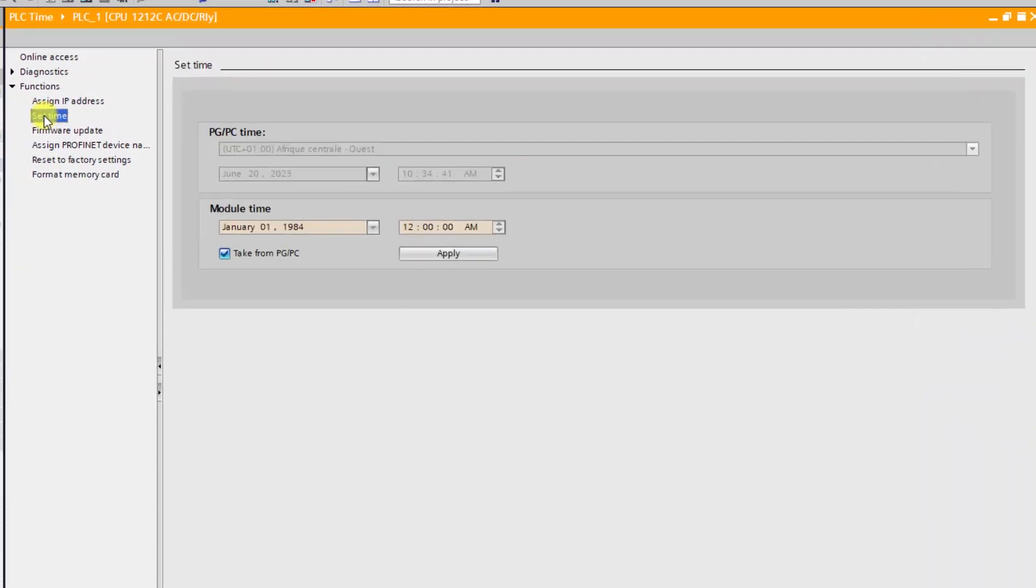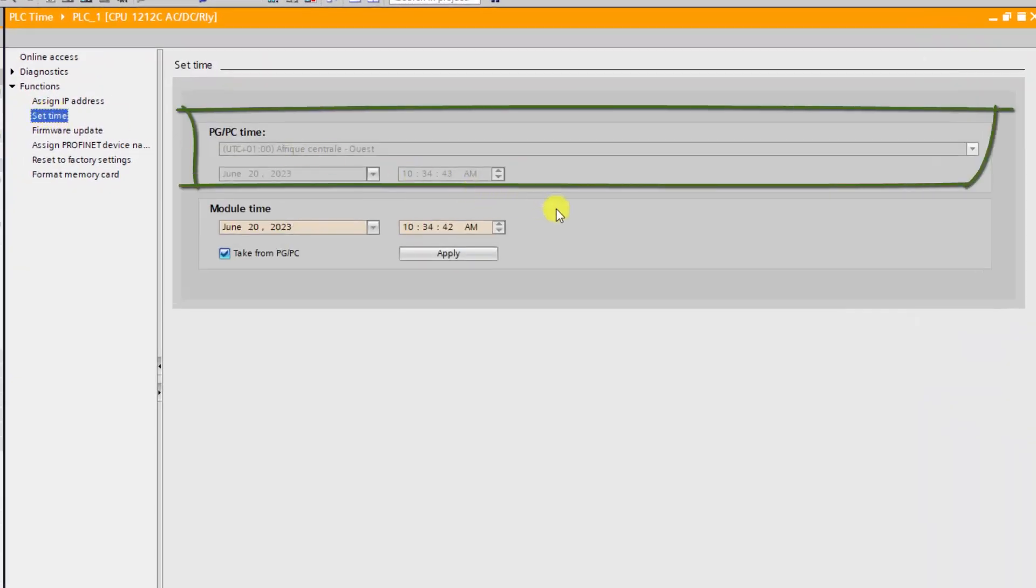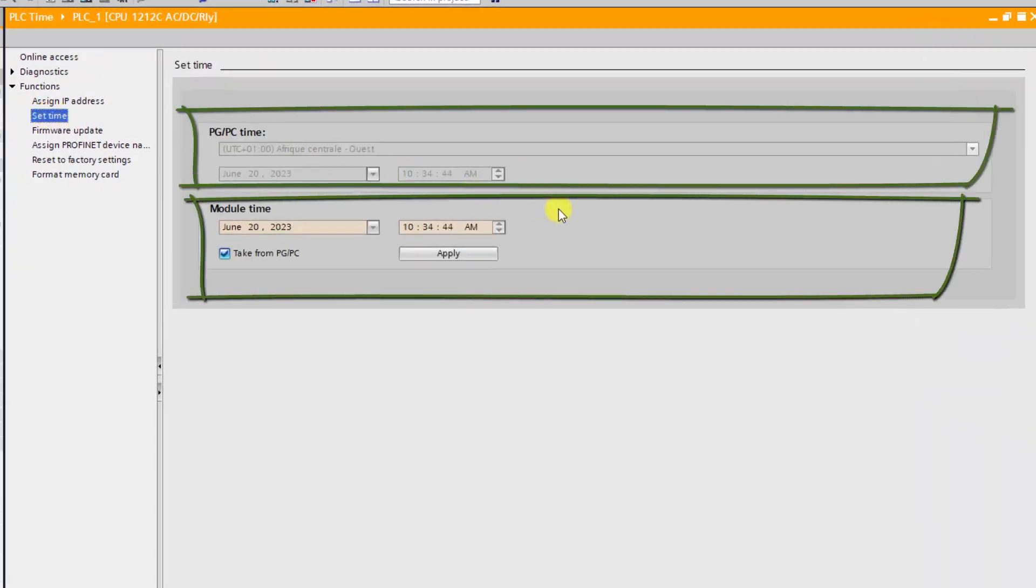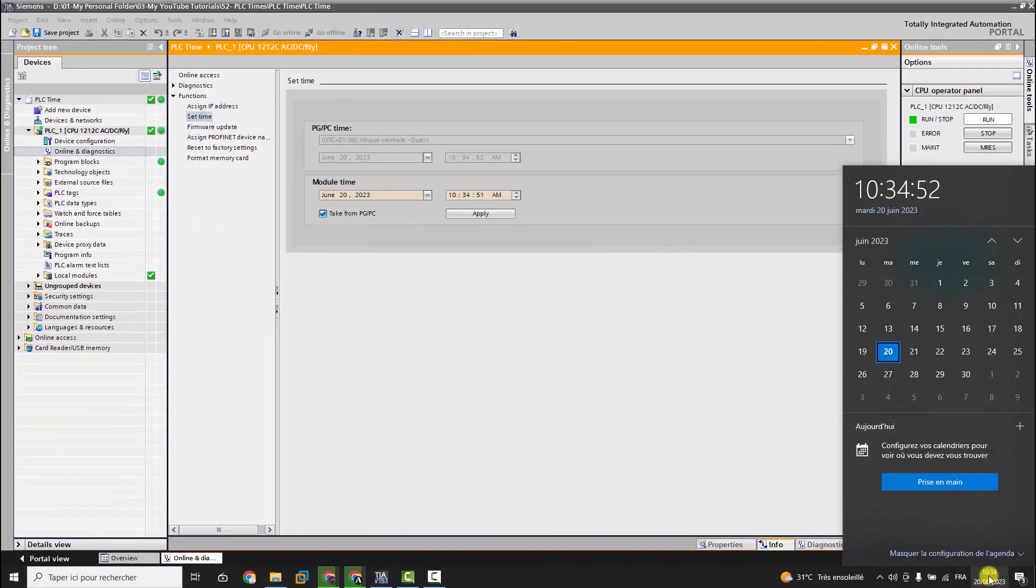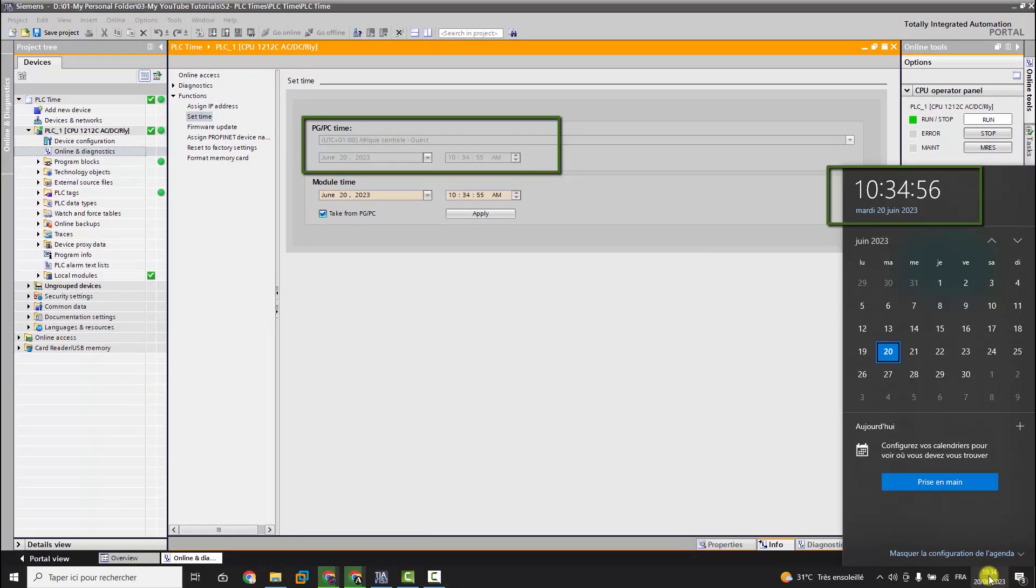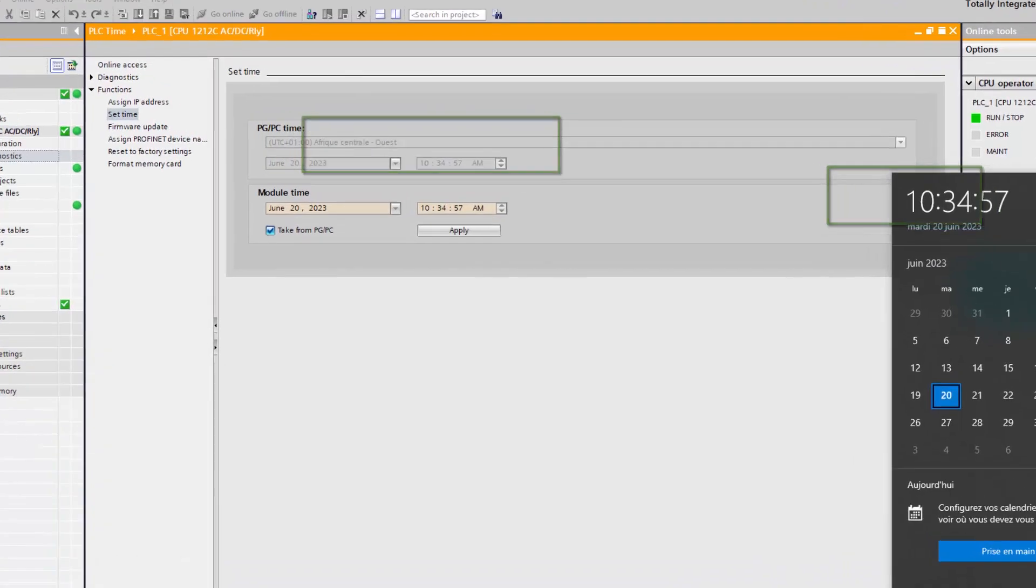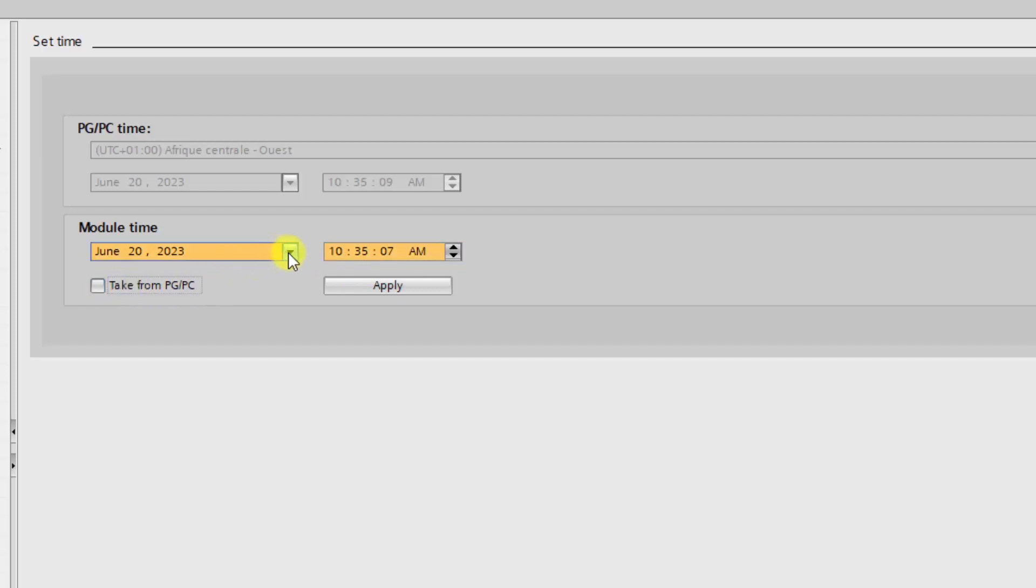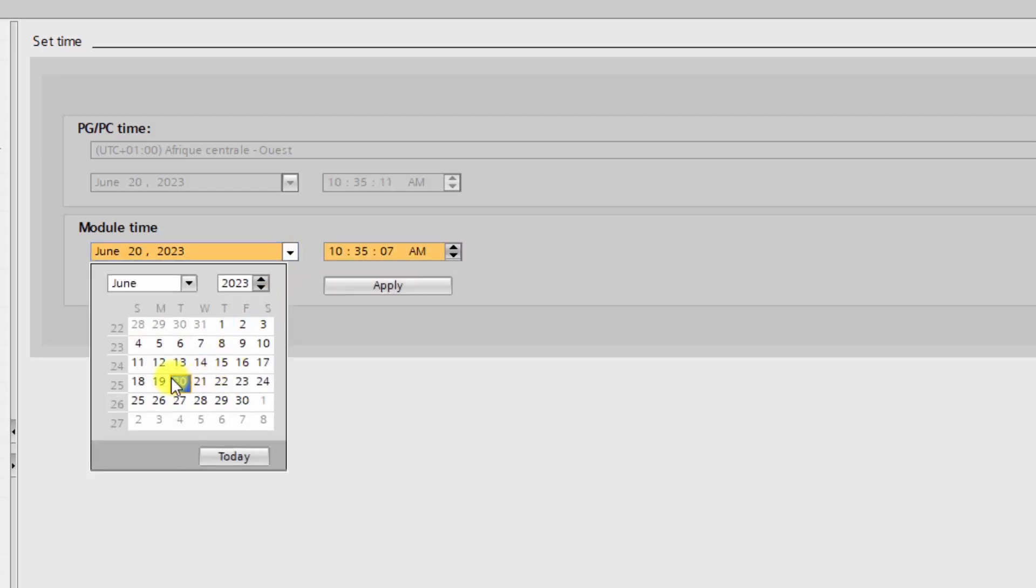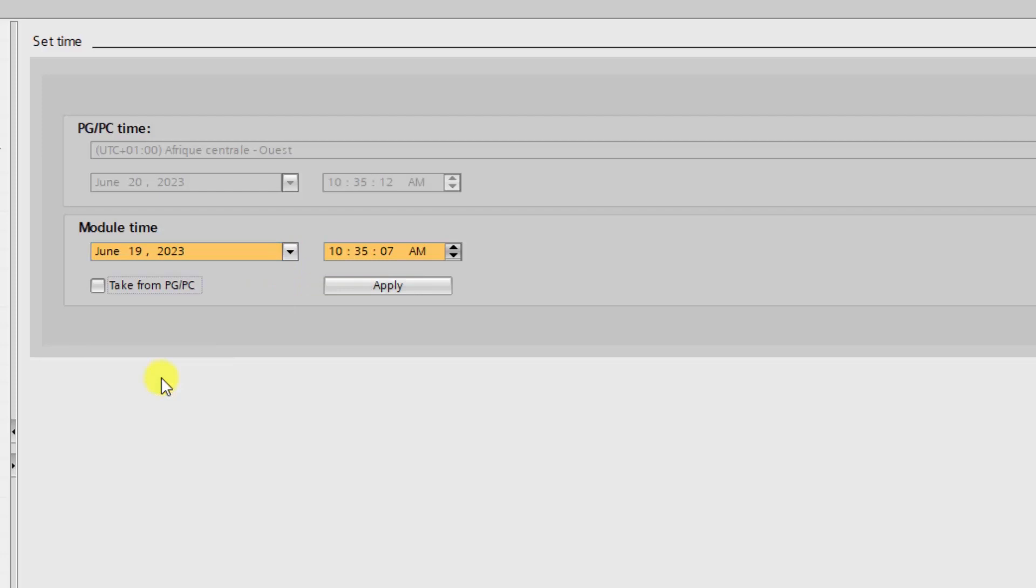Next, we click on Online and Diagnostics to enter online with the controller. Once it's done, we can click on the sub-menu Set Time. There we find two sections. The first is called PG/PC time - it refers to the actual time of your laptop. We can even check it. It has no relation with the PLC internal time. The second is called Module time - it is exactly the PLC internal time. Right now we can uncheck the box "Take from PG/PC" and then change the date and time manually and then click on Apply.